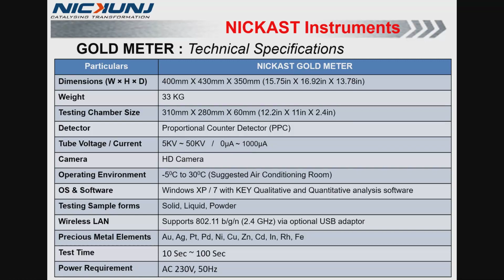The weight of the machine is 33 kg. The testing chamber size is 12.2 by 11 by 2.4 inches. Nickast gold meter has a proportional counter detector. The tube voltage is 5 kV to 50 kV. It has an HD camera. Operating temperature is minus 5 degrees Celsius to 30 degrees Celsius.